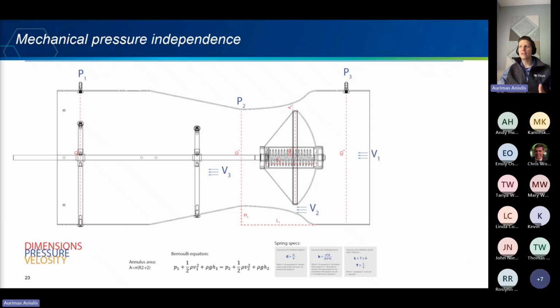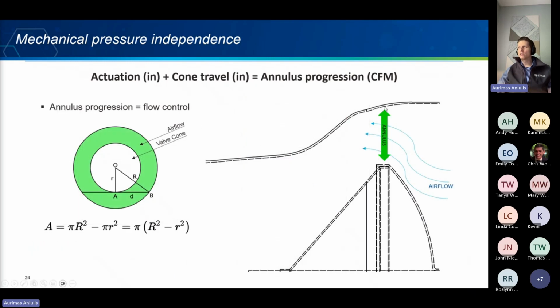This is a side slice view of the Venturi air valve. So your air is coming in as velocity 1, hitting the cone, and you see these little gaps around the cone for the air to pass through. That's all there is for the air to pass around this cone. And as more pressure hits it, this cone spring compresses and this gap becomes smaller. Well, that gap is called an annulus, and we're looking at a close-up of it here as the airflow passes through it and the cone spring compresses. The amount of air that it allows to pass through is reduced instantly.